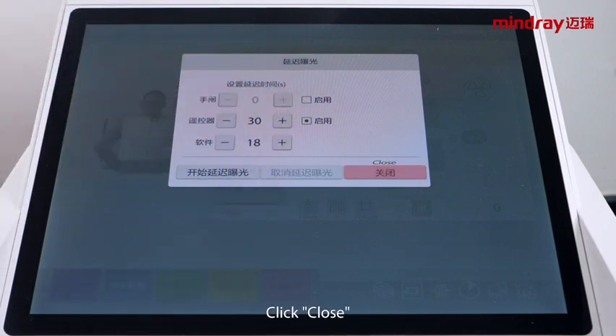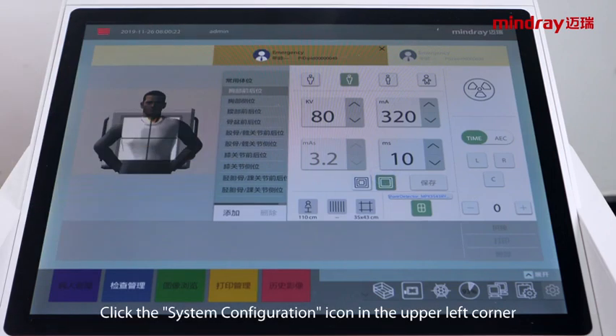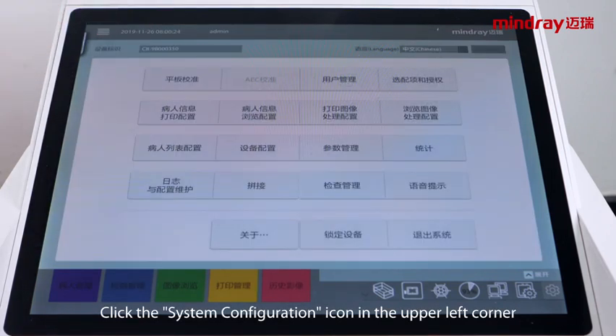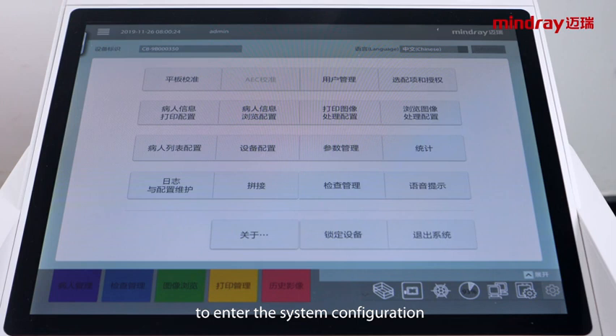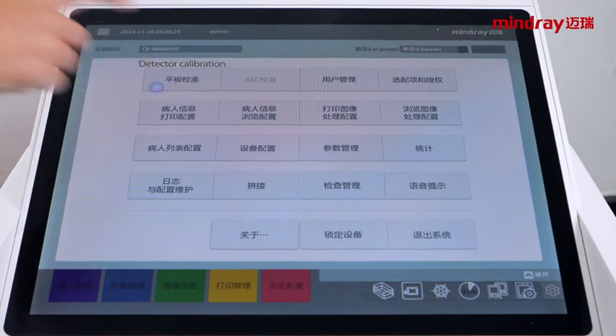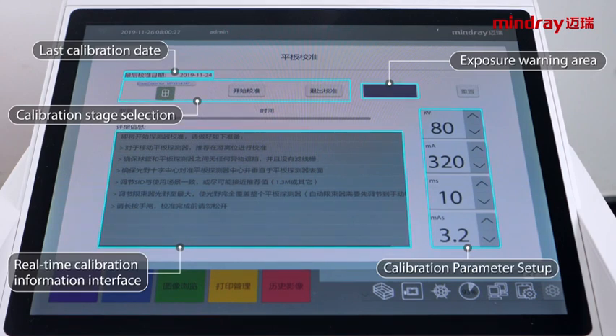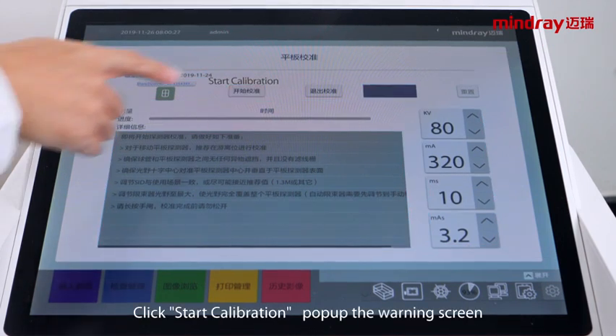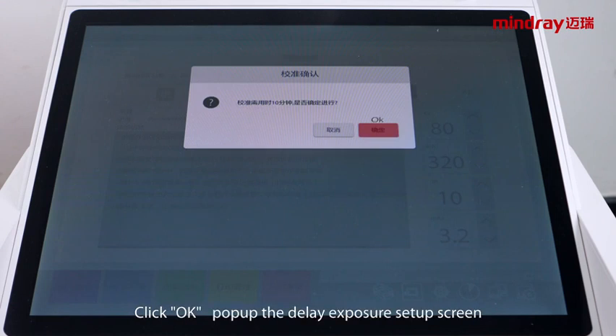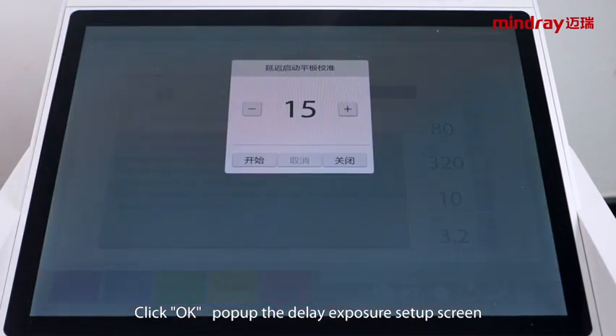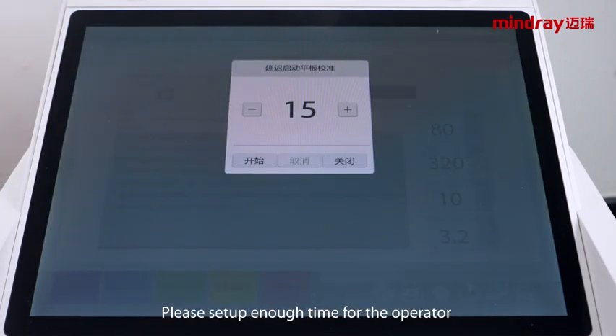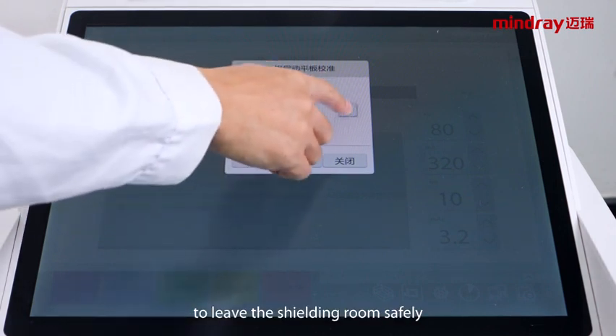Click Close. Click the System Configuration icon in the upper left corner to enter the system configuration. Click Detector Calibration. Click Start Calibration, and a warning screen pops up. Click OK, and the Delay Exposure Setup screen pops up. Please set enough time for the operator to leave the shielding room safely.